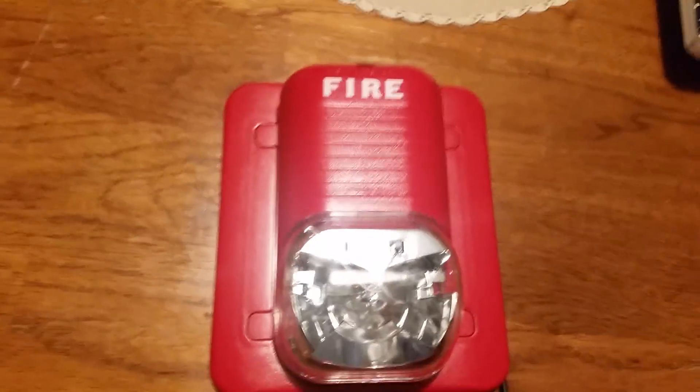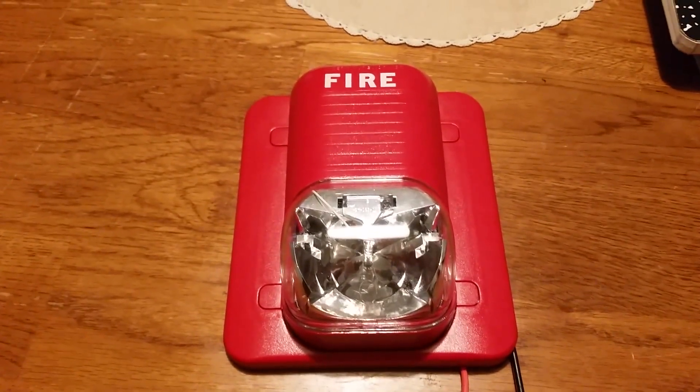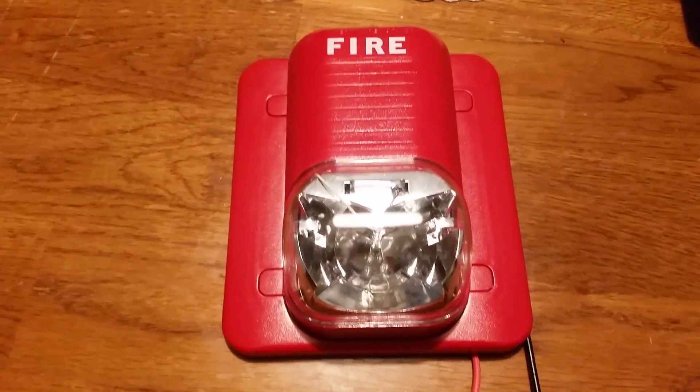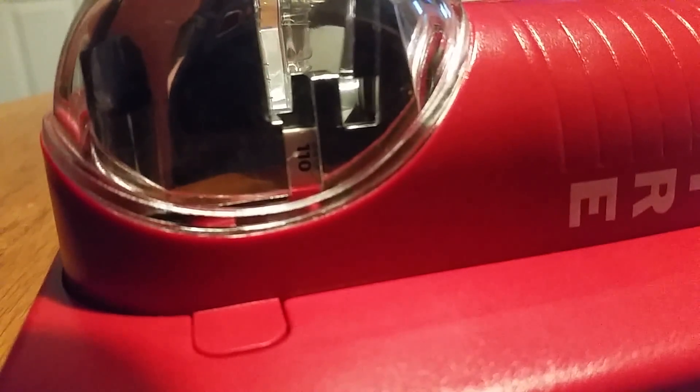Hey guys, this is going to be Fire Alarm Test 11. Today we're going to be testing the System Sensor S1224MC. It is a multi-candela strobe of the Classic SpectrAlert. I do have it set on 110 candela — you might have to turn your head sideways to see it. Yep, it's set on 110 candela.